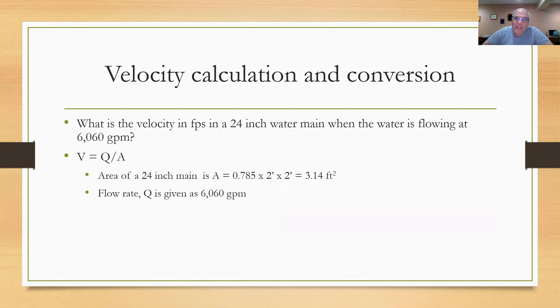For the formula V equals Q over A, the area of the 24-inch main can be calculated as 0.785 times the diameter squared equals 3.14 square feet. The flow rate is given as 6060 gallons per minute, not cubic feet. When I set up the equation and put 6060 gallons per minute divided by 3.14 square feet, that's not going to work. You got to change the gallons per minute or the square feet to make them match.